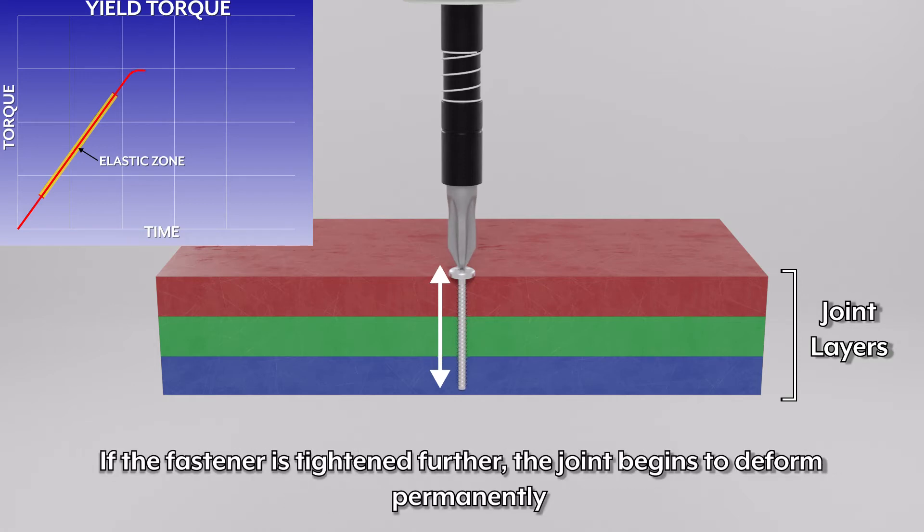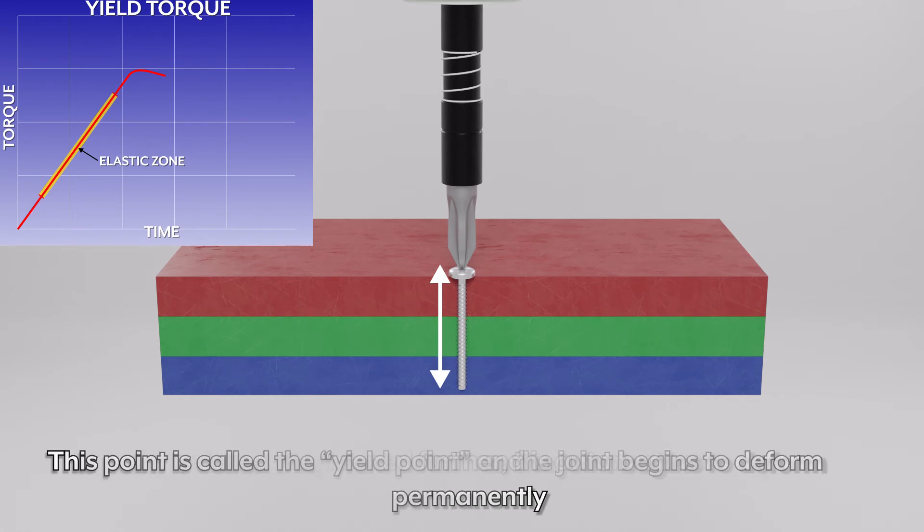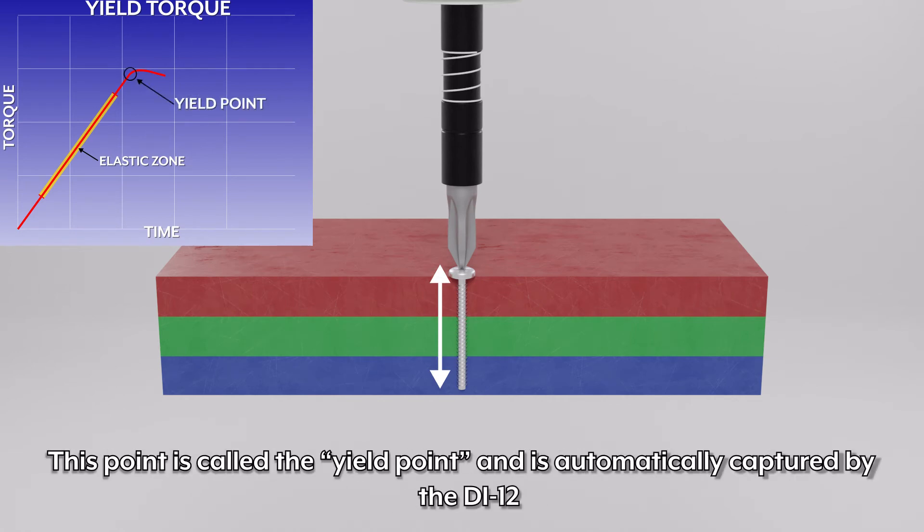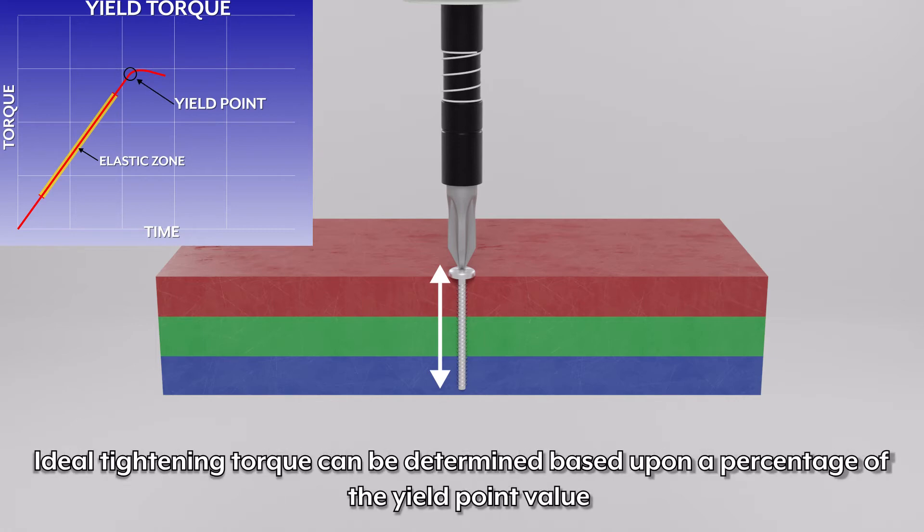If the fastener is tightened further, the joint begins to deform permanently. This point is called the yield point and is automatically captured by the DI-12. Ideal tightening torque can be determined based upon a percentage of the yield point value.